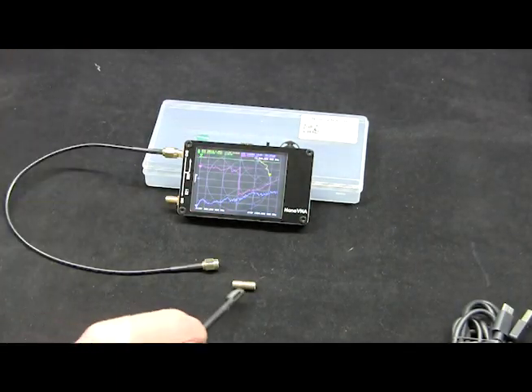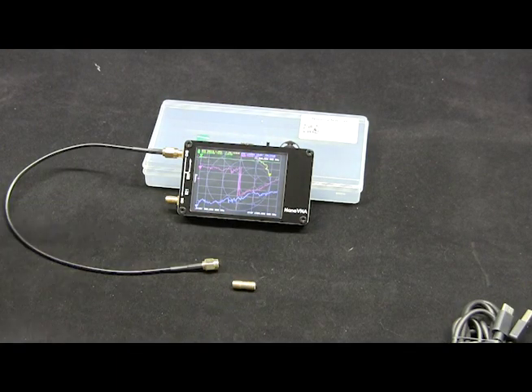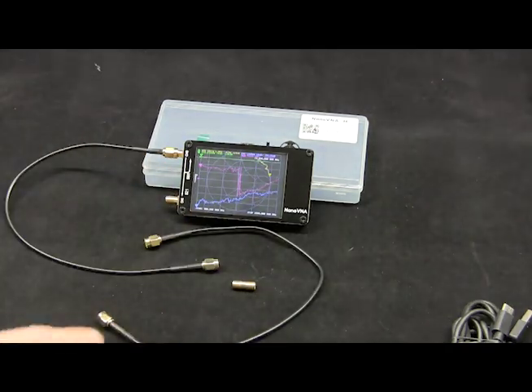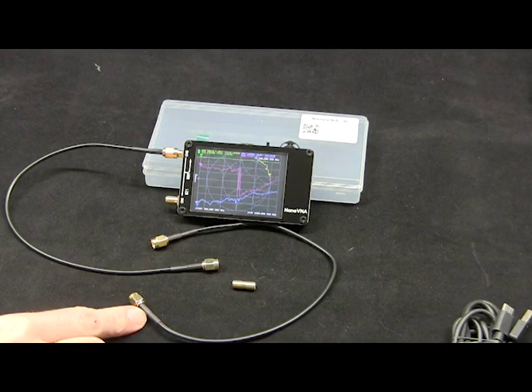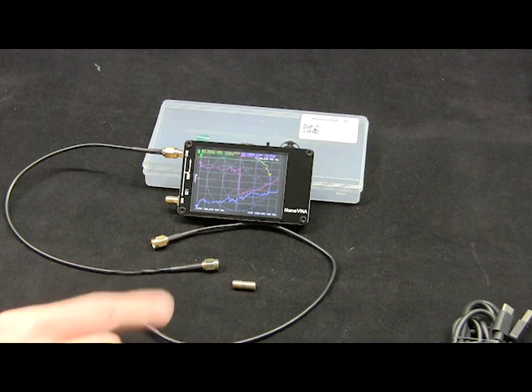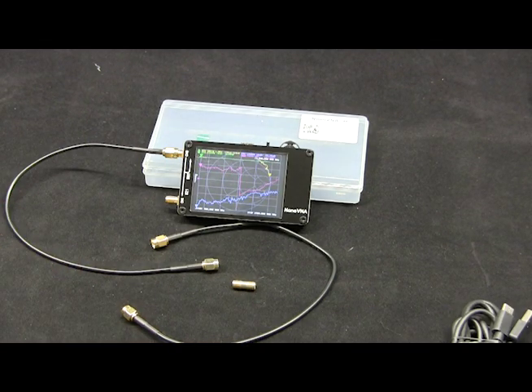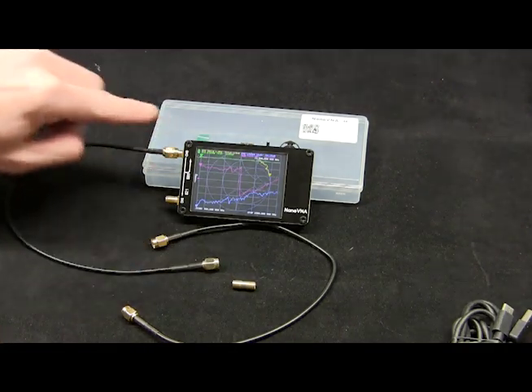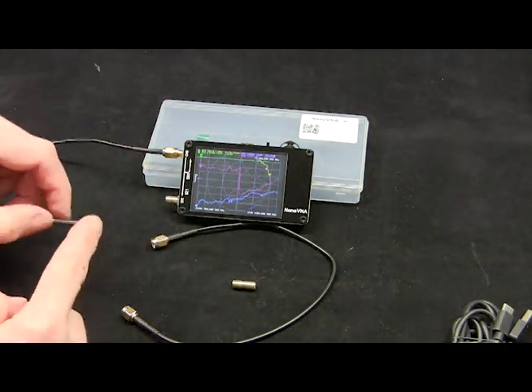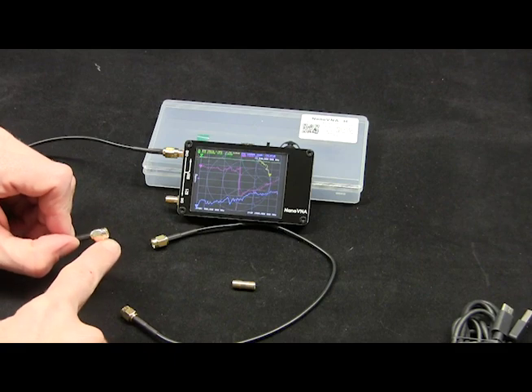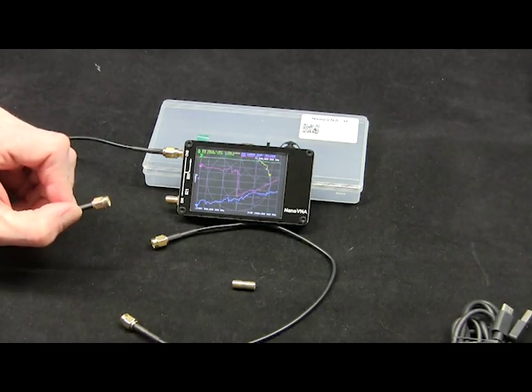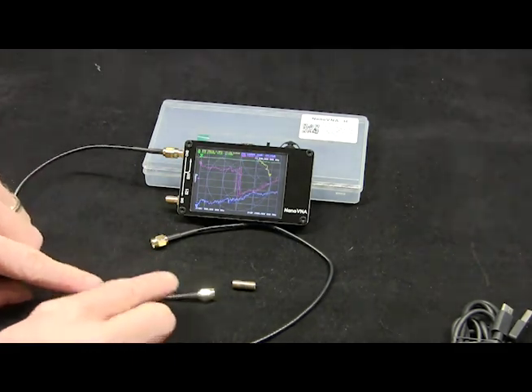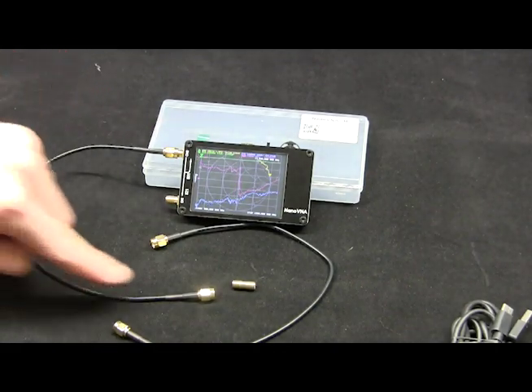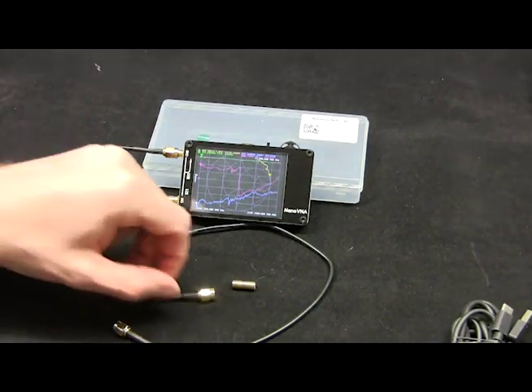All right, now that you've fully calibrated, you can simply take your calibrations out, but you'll need to leave your adapter. So the device we're going to test for this lab is this cable. We're going to measure the electrical length of the cable and its loss and the phase shift through the cable with our VNA. What's important to remember is we've calibrated the device to the end of here. So whatever we connect between this connector and that is what we're measuring. This cable is not part of the measurement because calibration removed all of the effects.